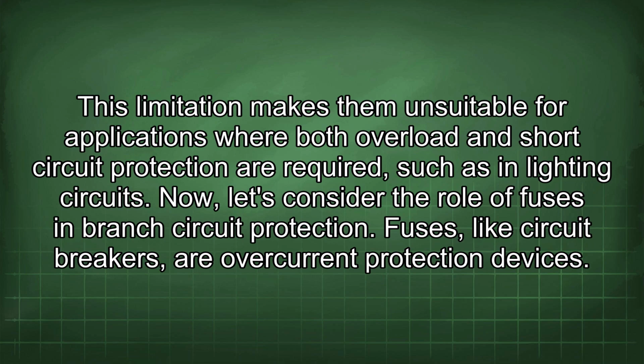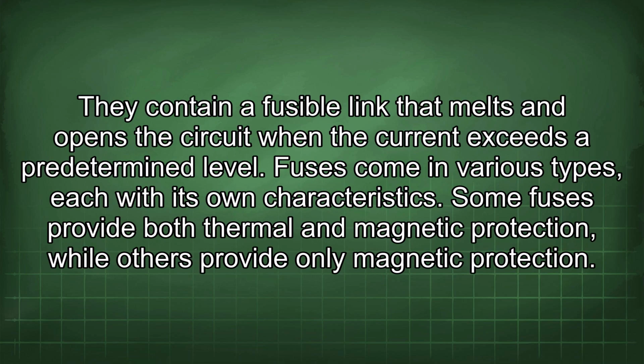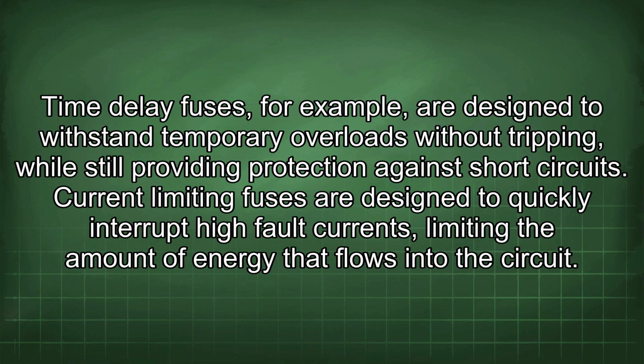Fuses, like circuit breakers, are overcurrent protection devices. They contain a fusible link that melts and opens the circuit when the current exceeds a predetermined level. Fuses come in various types, each with its own characteristics. Some fuses provide both thermal and magnetic protection, while others provide only magnetic protection. Time delay fuses, for example, are designed to withstand temporary overloads without tripping, while still providing protection against short circuits. Current limiting fuses are designed to quickly interrupt high fault currents, limiting the amount of energy that flows into the circuit.